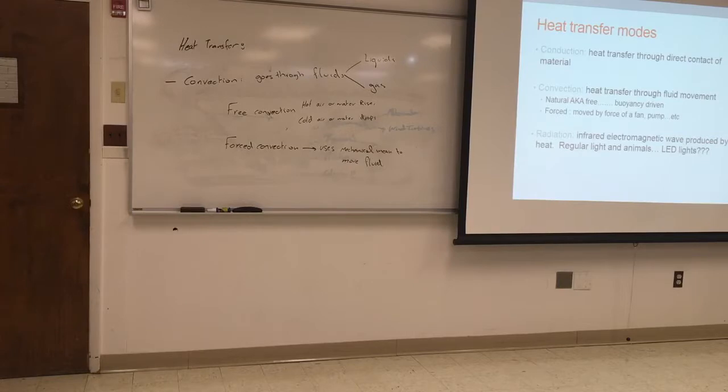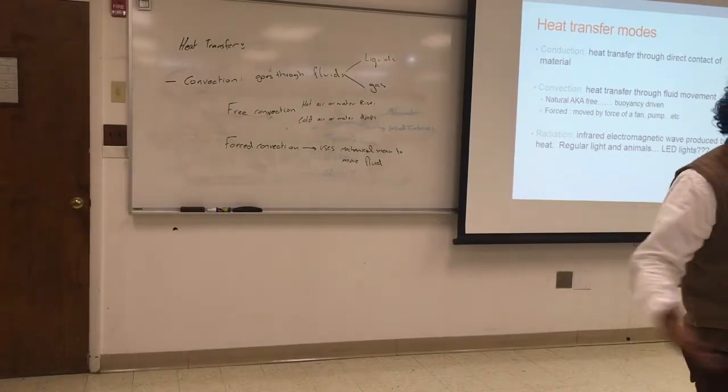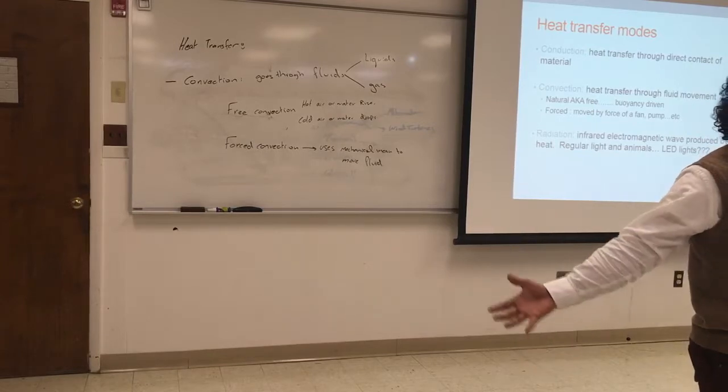Yeah, but it's not heating through convection or conduction. You heat the floor, and the floor radiates to the room. And if you notice, radiant floor heating is one of the best ways to heat a house because it does not have to be too hot. 85 is enough. And because we're using the floor, it's a big surface area, it will radiate to the room.